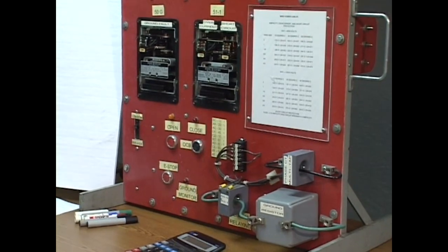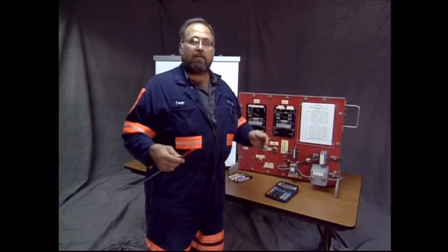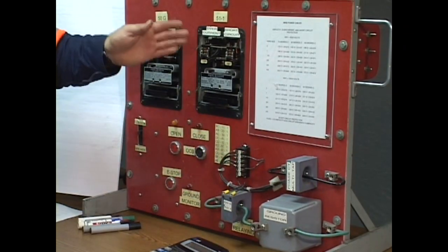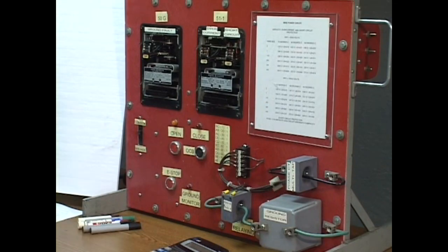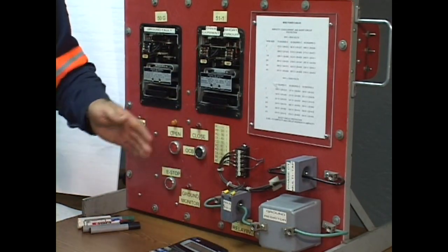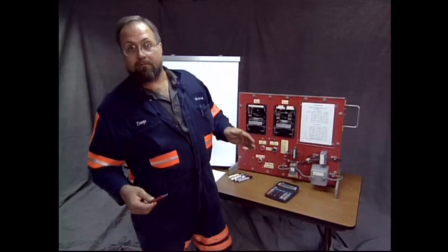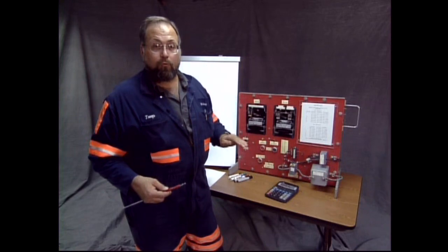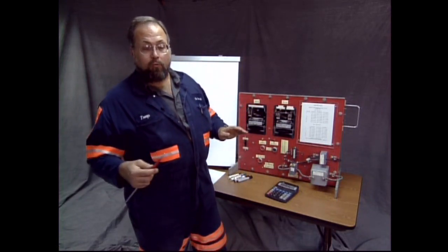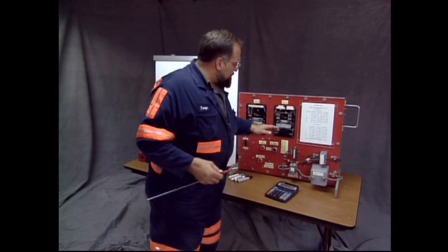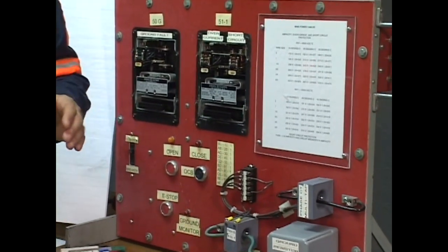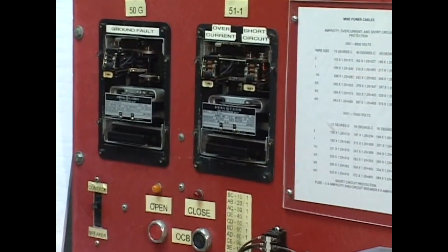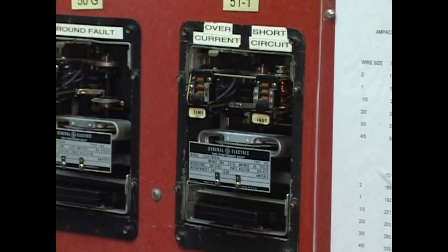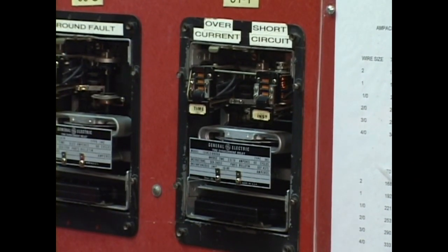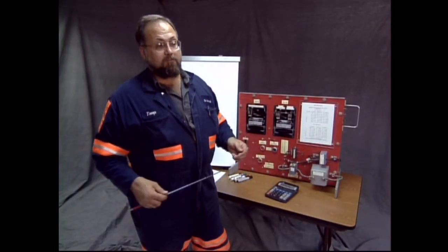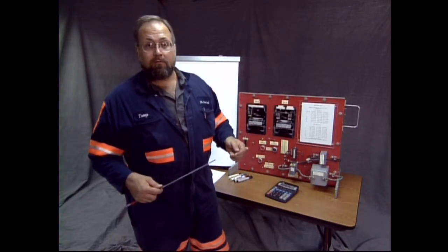Now, overcurrent and time go together. Short circuit and instantaneous. You'll note that the same CT provides both time, or overcurrent, and short circuit. Time and instantaneous are both supplied by the same CT. In your overcurrent settings, they don't begin until 10. 10 is usually your first number for your core setting for short circuit. A core setting of 10 is the minimum. And on this device, it ranges from 10 to 80. Well now, that's a lot of current for that CT that's only rated for 5. What makes that an acceptable number, though, is the fact that it's instantaneous. There's virtually no sustained fault. That's the major difference between an overcurrent and a short circuit.